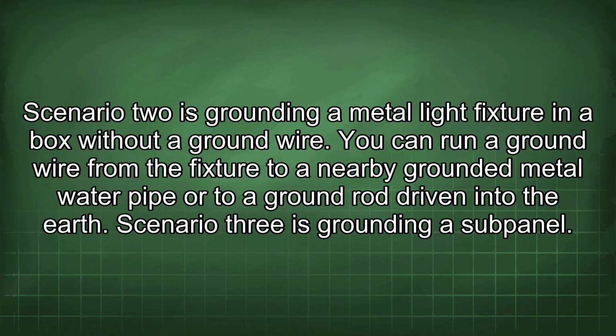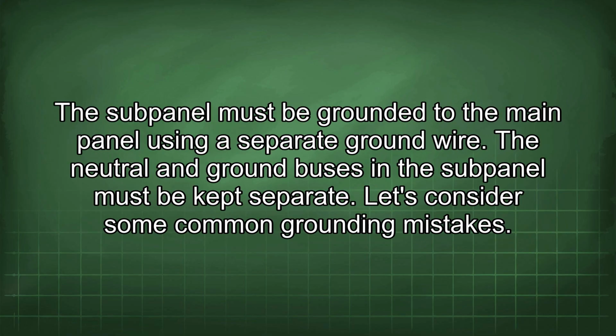Scenario 2 is grounding a metal light fixture in a box without a ground wire. You can run a ground wire from the fixture to a nearby grounded metal water pipe or to a ground rod driven into the earth. Scenario 3 is grounding a subpanel. The subpanel must be grounded to the main panel using a separate ground wire. The neutral and ground buses in the subpanel must be kept separate.